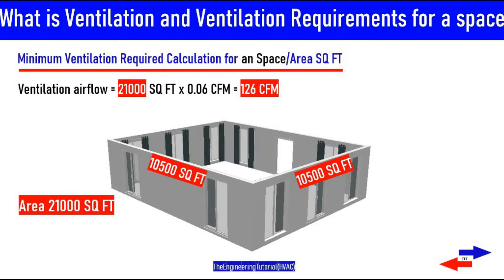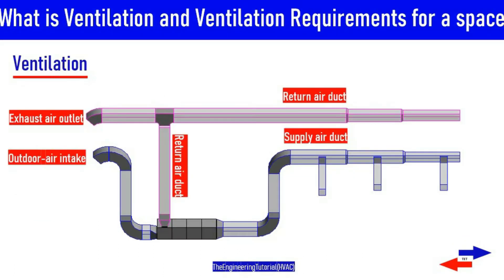Outdoor air is often used to dilute or remove contaminants from indoor air. The intentional introduction of outdoor air into a space through the use of a building HVAC system is called ventilation. The outdoor air must be cooled and dehumidified before it can be delivered to the space, creating an additional load on the air conditioning equipment. You shouldn't depend on infiltration air to satisfy ventilation requirements, since when outdoor air is not moving due to wind, infiltration can drop to zero.